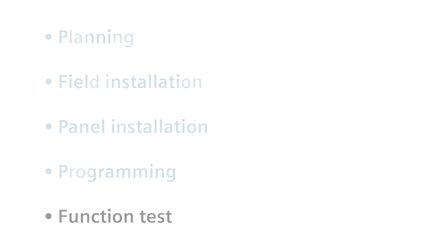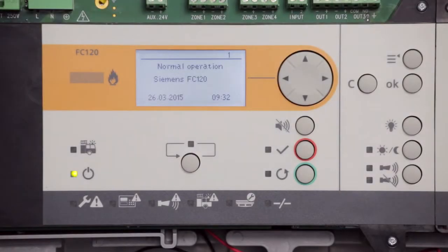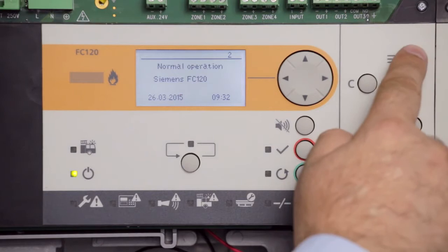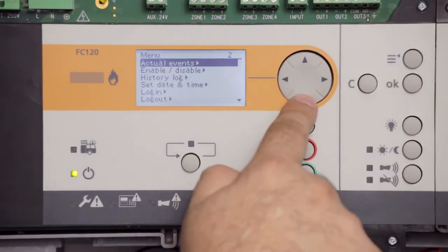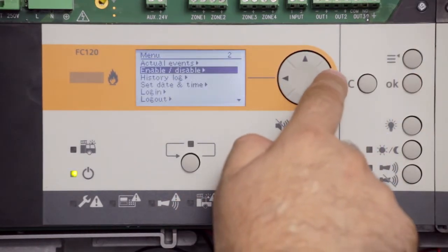Let's test the panel. So we've completed the basic programming. What we have to do as our final step is to test the installed equipment. In our demonstration, we will focus only on the detectors. Enable the test mode for each zone. Press the menu button. Select Enable or Disable and confirm.